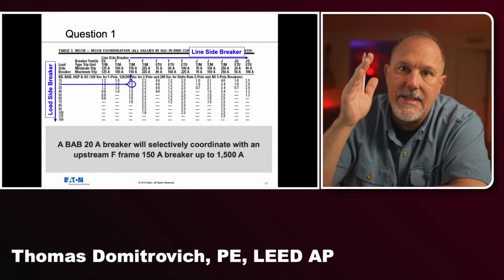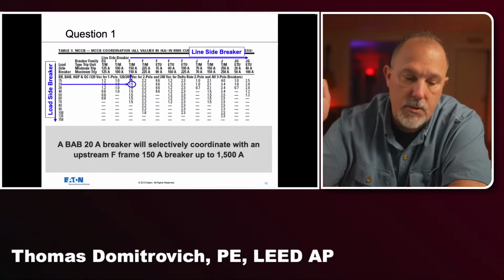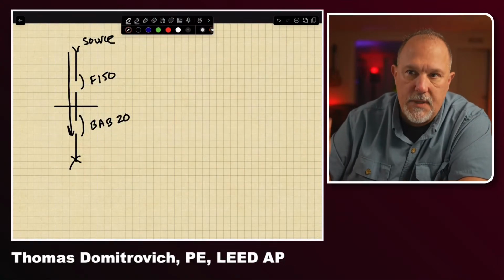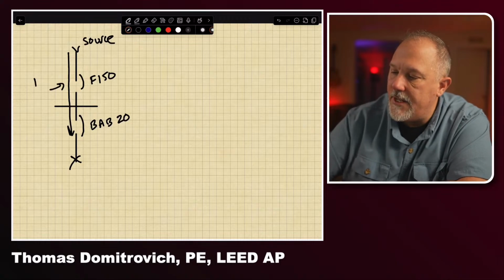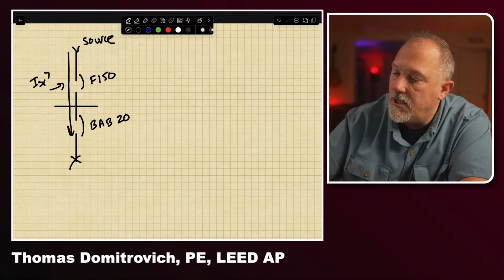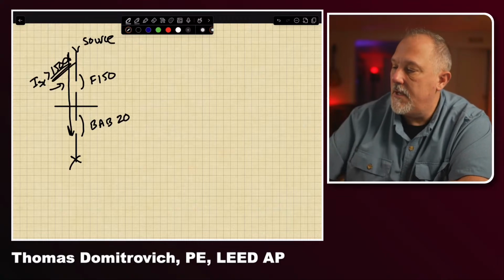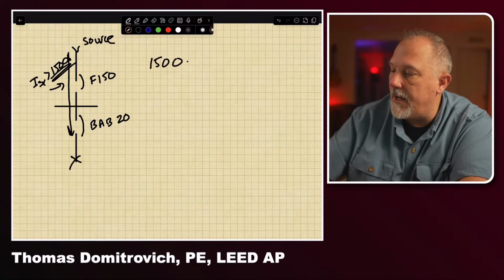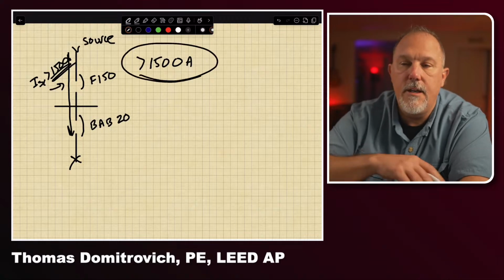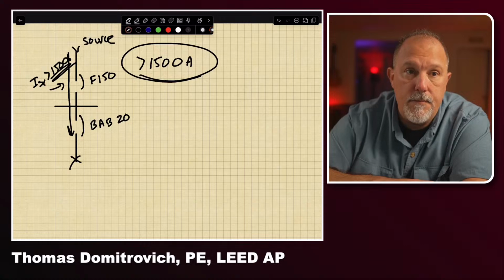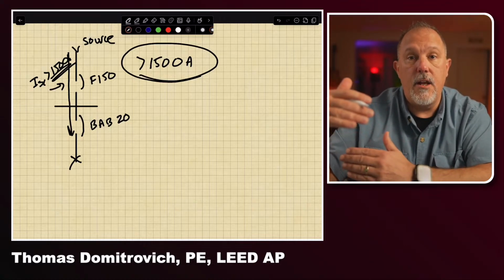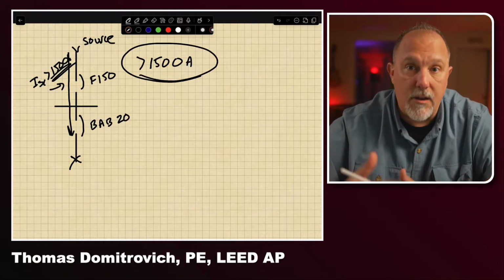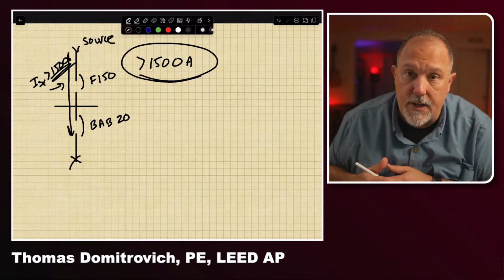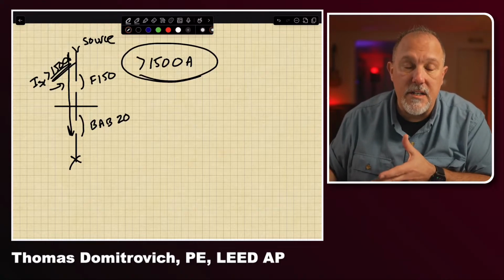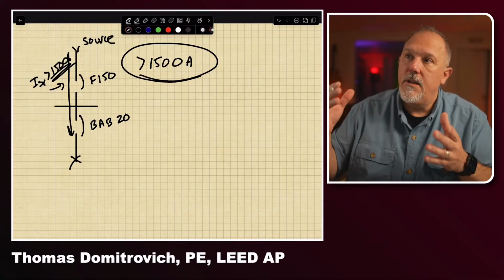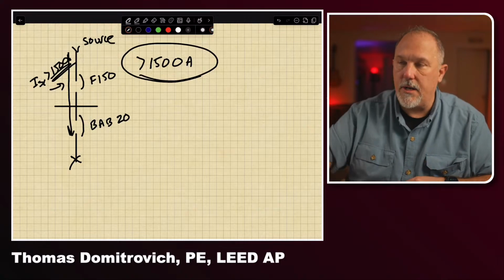So what I can definitively tell you, based upon the tables and based upon the testing, is that when the short circuit current for this pair of breakers is greater than 1500 amps, then they will both open. And you don't have selective coordination. And I don't care if that is a three-phase bolted fault current value. I don't care if it's a ground fault current value. I don't care if it's an arcing fault current value. What I do care about is that it's an RMS current that is passing through there. Okay? So that is going to cause both of those circuit breakers to open.